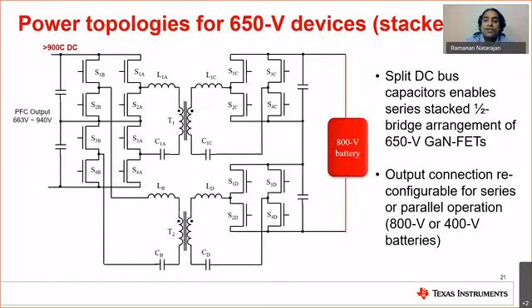Now let's look at the stacked half-bridge arrangements. We spoke about multi-level converters, but there's another commonly used arrangement which is called the stacked series half-bridge. This shows the example of a DC to DC converter, which is running off of a high DC bus over 900 volts DC. On the primary side, you have 650 volt devices arranged as a stack of 2 half-bridges in series on the primary side, and then you have half-bridges on the secondary side, which are operating between 2 split capacitors. The way the transformers are driven is between the switching nodes of the 2 half-bridges on each stack, which is then unfolded and rectified on the secondary side.